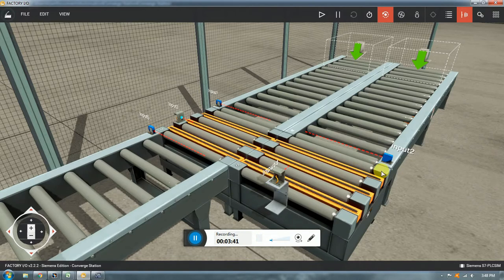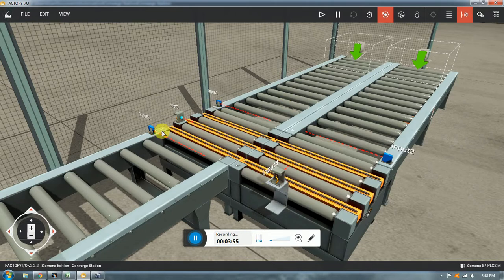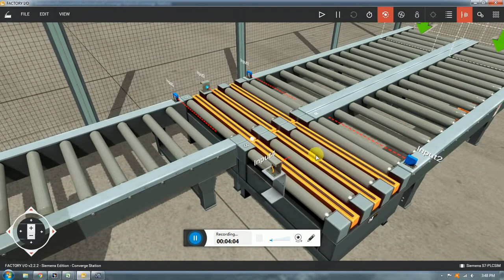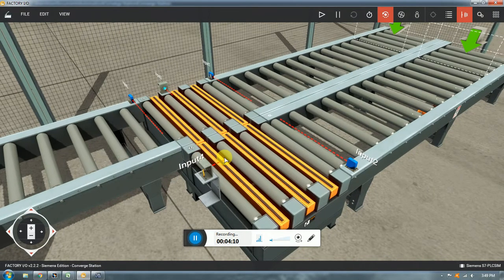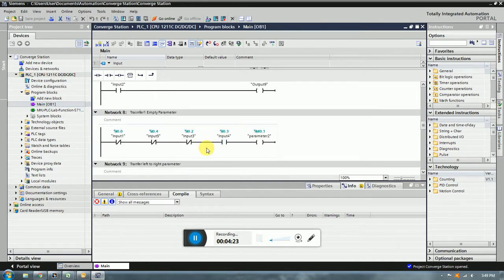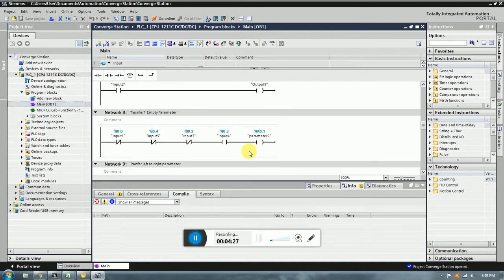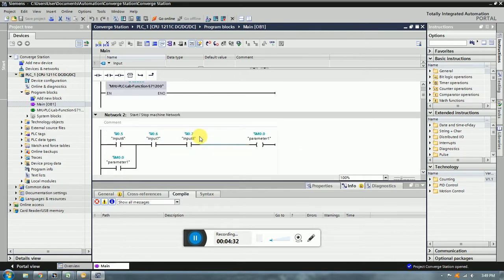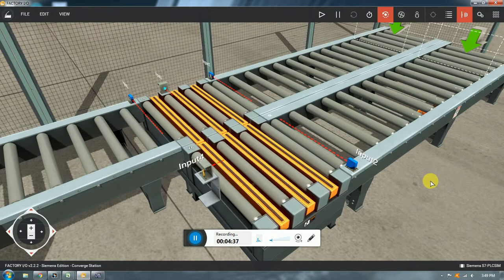I would suggest that even if you want to play with different sensors, just make them all be on the same page. If you want normally closed sensors, put everything as normally closed. If you want normally open, use everything normally open. If you mix them, you may have a little chaos — it may give you extra problems. Sometimes issues are obvious, but it's not easy to see when you have more than five lines. These sensors are one of the most important parts of the whole assembly system.